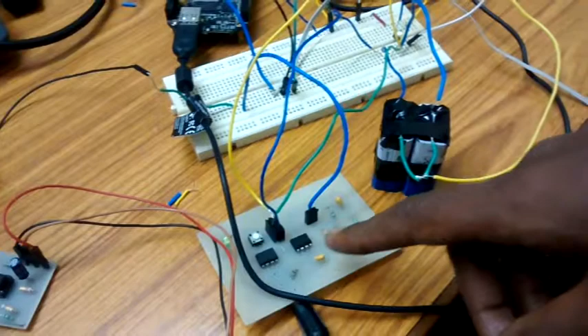Now I'll describe the functioning of the ECG. For the ECG, we have used the instrumentation amplifier INA128, which is also manufactured by Texas Instruments, and we have used LM358 as the bandpass filter. The instrumentation amplifier takes the signal from 3 leads: left arm, right arm, and right leg. We have created the bandpass filter so that the minimum frequency is 0.3 Hz and the maximum frequency is 30 Hz. This is to reduce the noise in the circuit or in the surroundings.